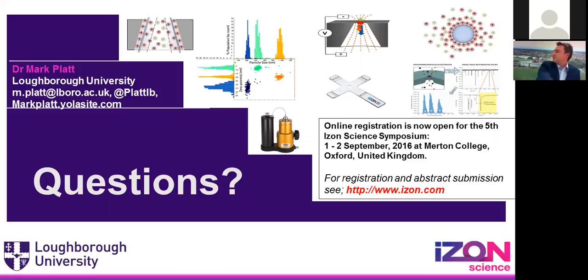So how does the pore size and the particles affect it, and you've seen the effects of applied pressure on the system and voltages. I guess for the pore size, optimizing the signal so that you can see a really nice pulse, first of all, would be the key thing. If you're missing some of the pulses, or the pore is too small and starting to restrict the particles as they go through, there is an impact on velocity.